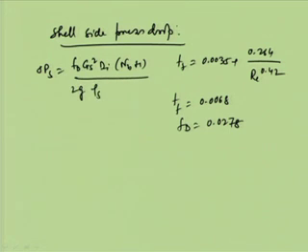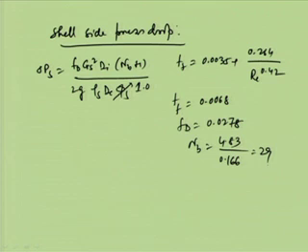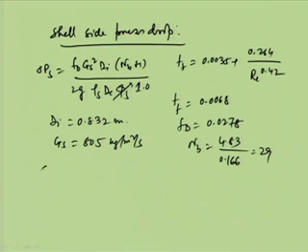2g rho s dE into phi s equals 1.0, and NB is equal to 4.83, the length of the tube exposed to the water, and the rest of the part is in the tube sheet, divided by 0.166, the baffle spacing, and this becomes 29. So, if we put all the values over here, DI is known to us as 0.832 meter, and all other values are known.